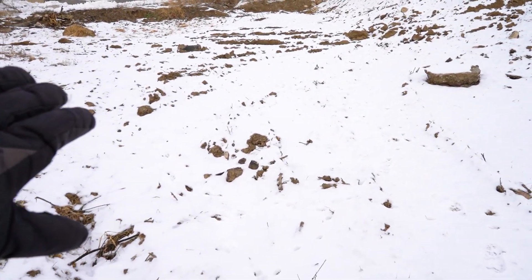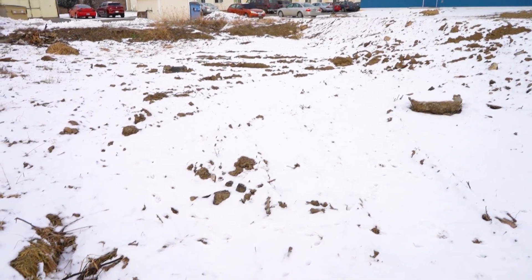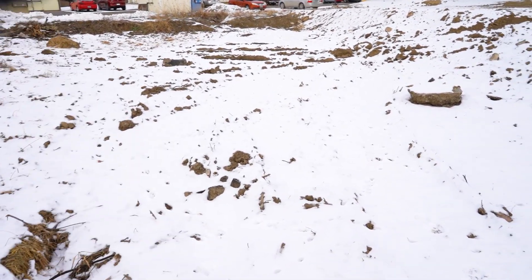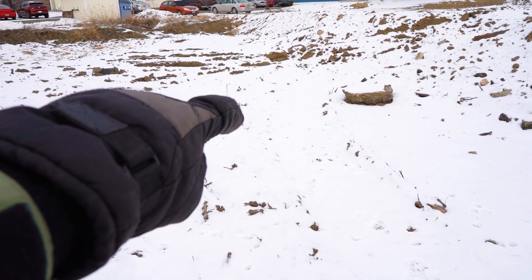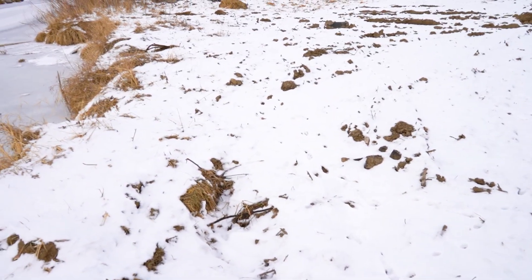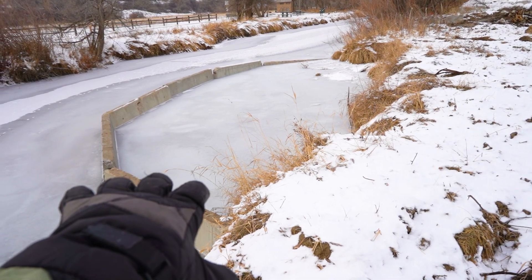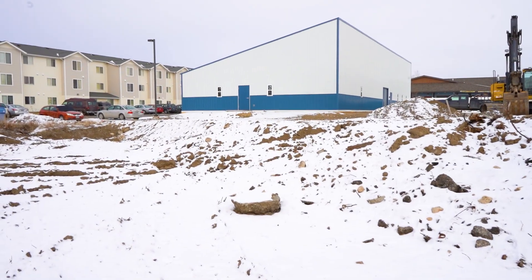This whole area is going to be excavated — about 40 feet by 40 feet or so. In the middle is where that cistern will go, with all these pipes running this way with holes to collect water as it flows from the creek through the gravel and rock and into those pipes. That'll go into the cistern and be pumped up to the warehouse. Going through gravel and rock gets it cleaned — it removes particulates and sediment. If we drew directly from the creek we'd get a lot of sedimentation. If the filtered collection ever isn't fast enough, we can turn a valve and collect directly from the creek as a fail-safe.